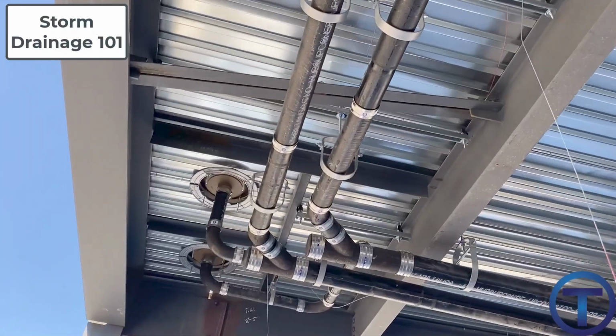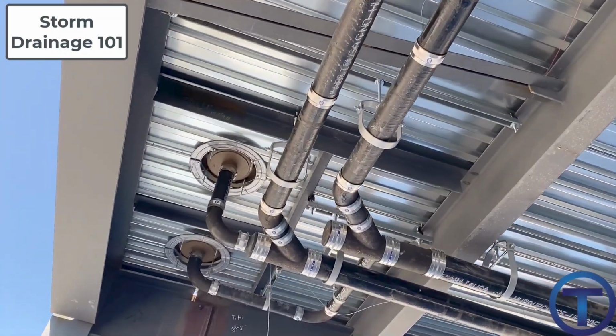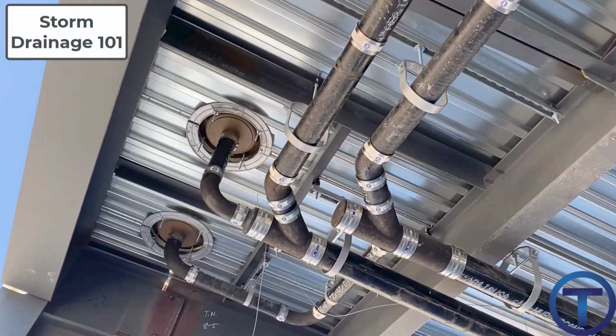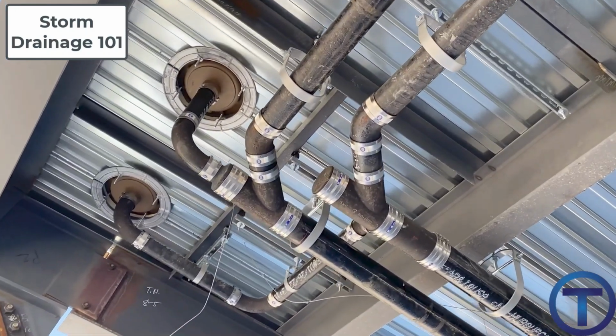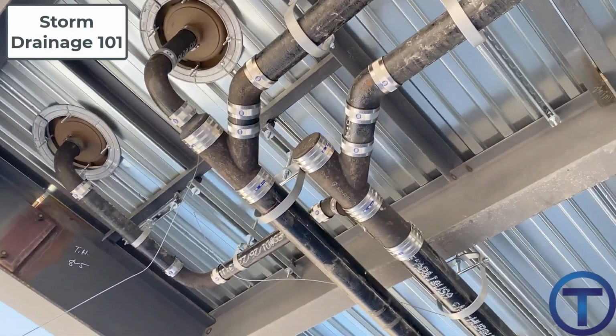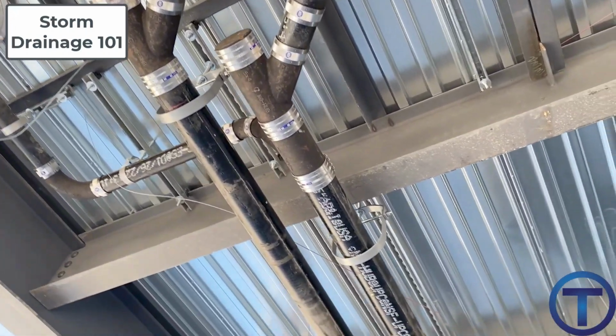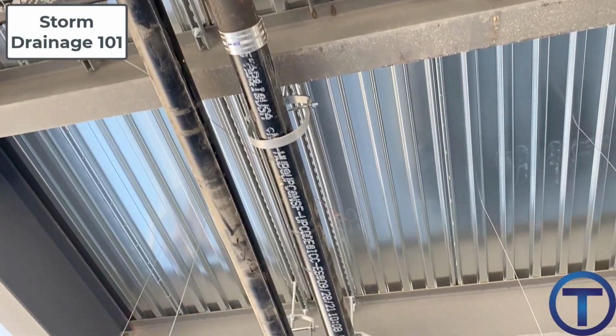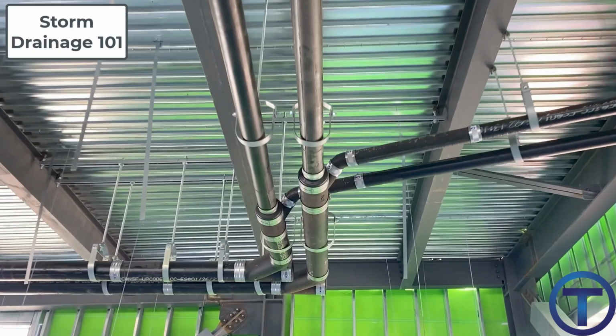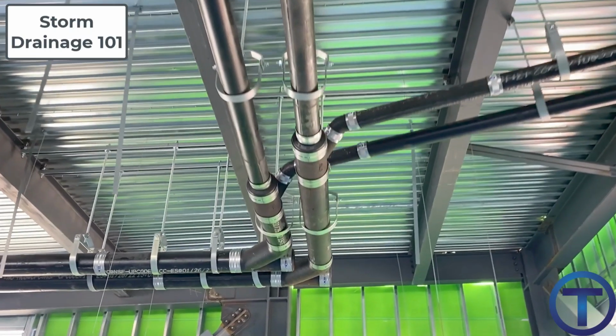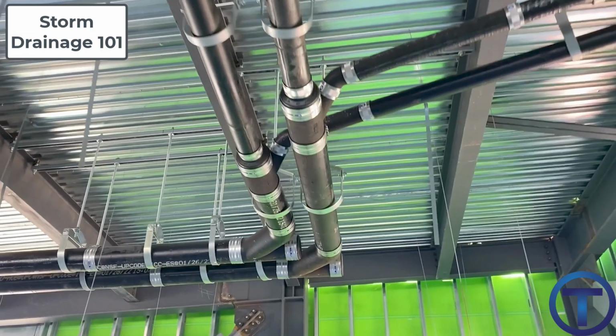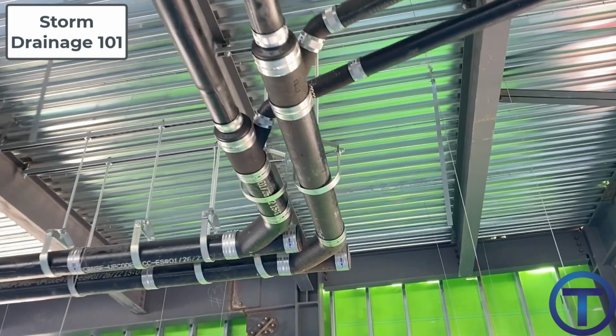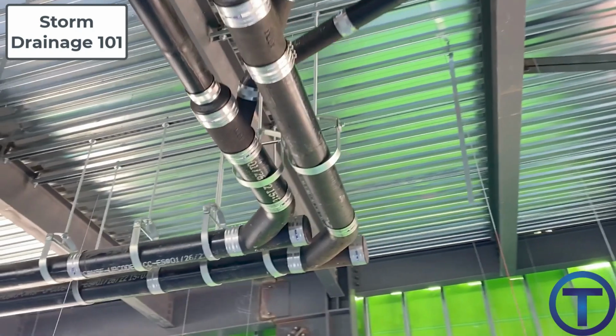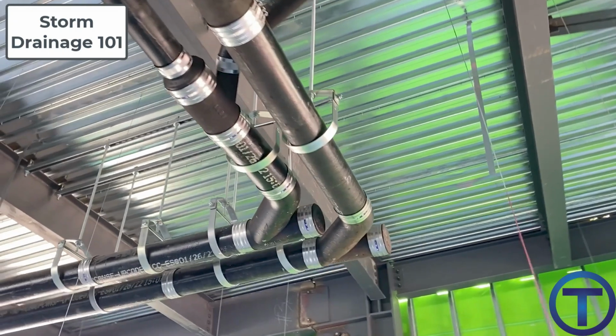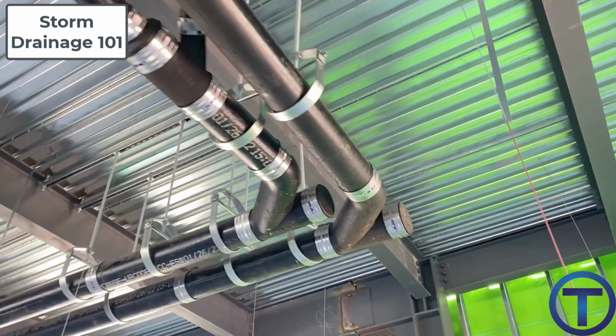Now, it is okay to branch these drains together. So you may have several sets of roof drains that run together into a larger roof drain, and then that is delivered out to the storm drainage system or the overflow. In those cases, it's very important that you don't cross the primary and secondary drain connections. These are two completely independent systems, and you wouldn't want to have any cross connections as those are installed.